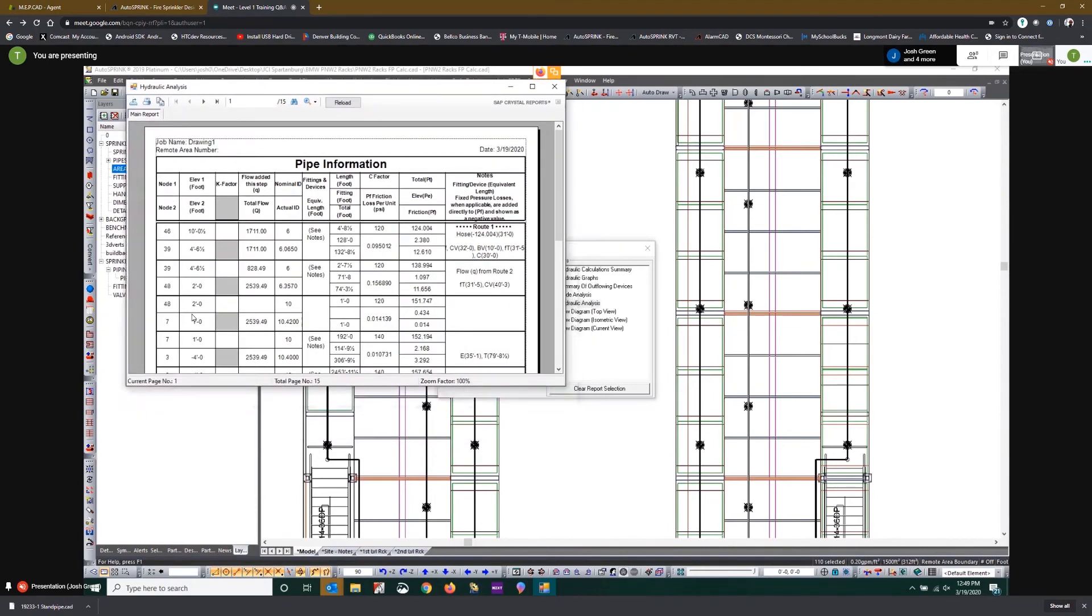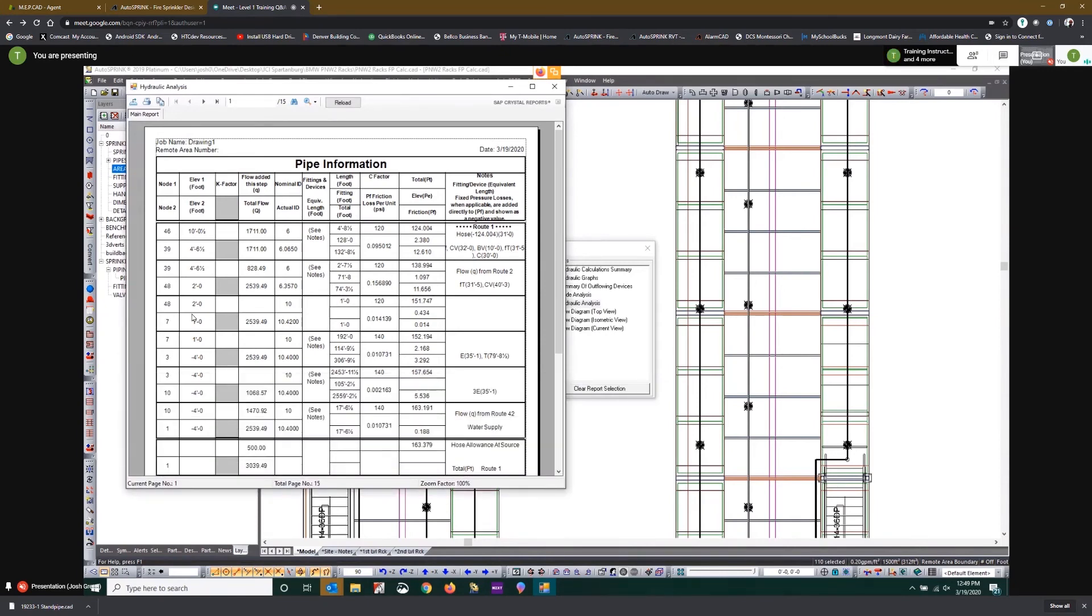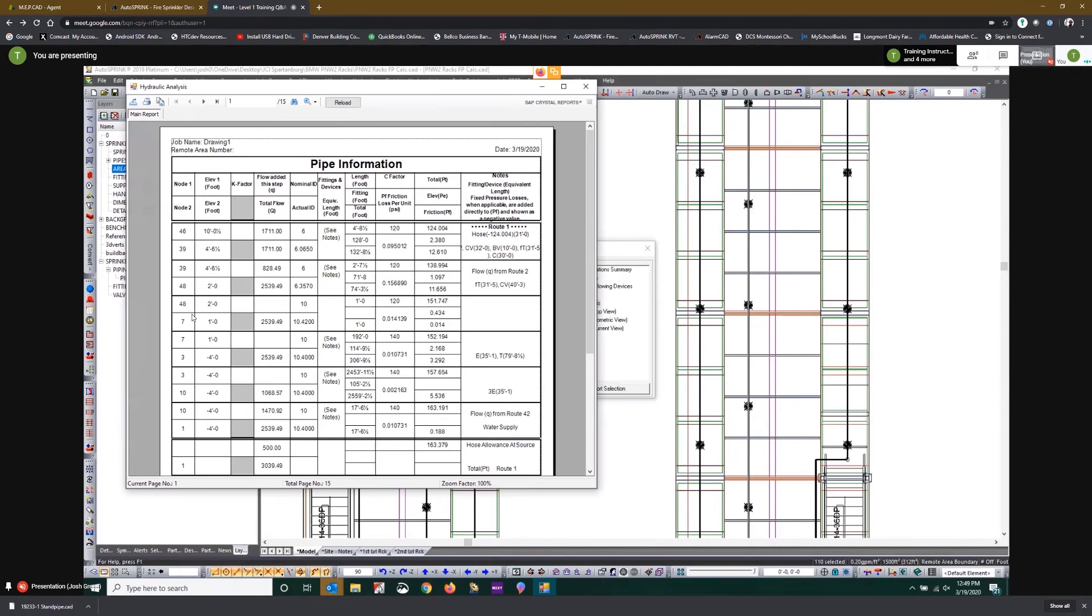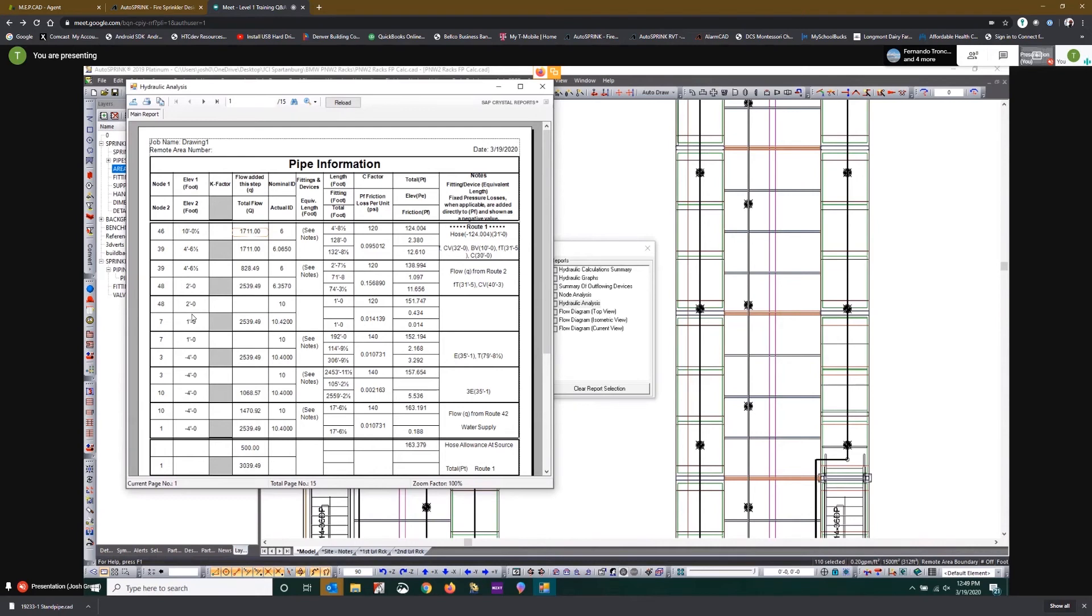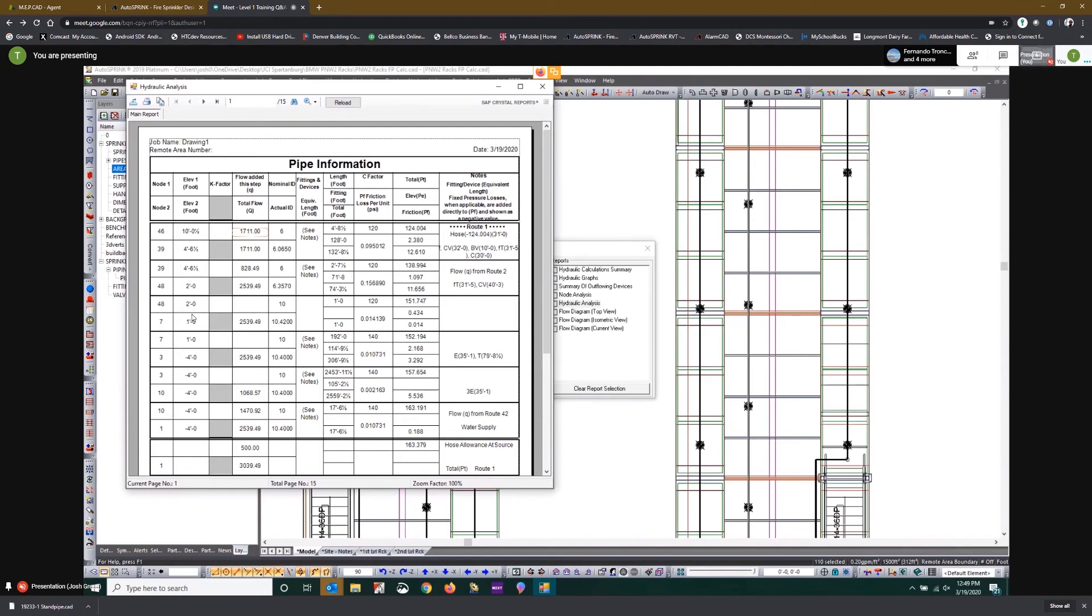Now if we change the flow state of that hose valve to pressure dependent flow, the program is going to lock that k-factor that we've established based on a minimum pressure, minimum flow, and it's going to adjust that flow rate based on the k-factor and the required pressure at that point based upon the demand of your in-rack system. So that flow rate is probably going to drop significantly, which may not be appropriate for this scenario because if that's a minimum required for that existing system, you certainly don't want to calculate less than that value. No, we want to make sure we're accounting for an accurate overhead demand.